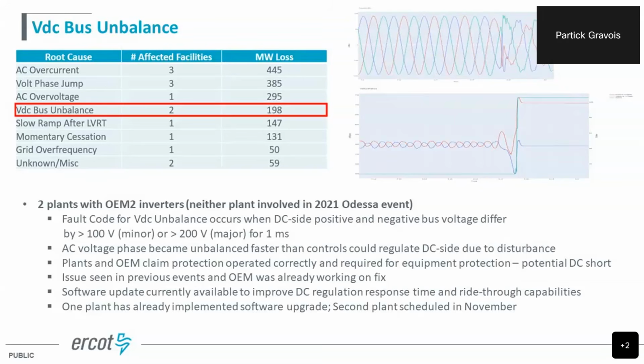This is something that had been seen in previous events, not in events at ERCOT, but I believe in California. So the OEM was already working on a fix for this. They already had a software update in testing at the time of this event. It has finished testing, and it would improve the DC regulation response time, basically speed that up to improve the ride-through capabilities to not trip off these inverters. So of these two plants, one plant has already implemented the software upgrade, and the second is scheduled to have this implemented in November.